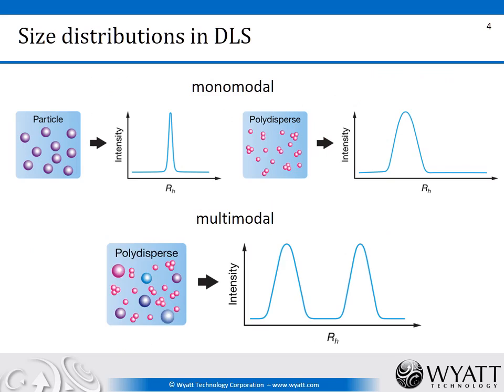To illustrate the types of distributions measured in dynamic light scattering: monomodal distributions show a single peak, and we can measure its average value and polydispersity. If the particles are polydispersed — for example, containing monomers, dimers, and trimers — that leads to an increase in the width of the peak, presented as polydispersity. If we have a multimodal sample, that means populations with two very distinct average sizes, each with their own polydispersity.